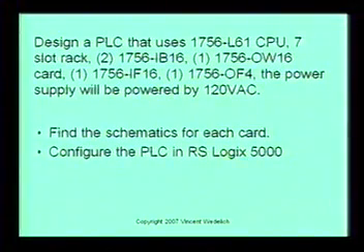Okay, the next problem, I guess that's problem number 19, is design a PLC that uses a 1756-L61 CPU, a 7-slot rack, two 1756-IB16 cards, one 1756-OW16 card, and then one 1756-IF16 card, and one 1756-OF4 card. The power supply will be powered by 120 volts AC. Find the schematics for each card, and then configure the PLC in RSLogix 5000.